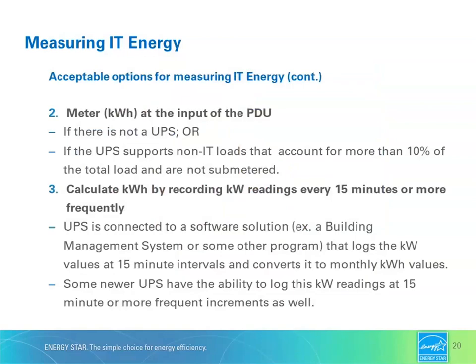So on to option number 2, metering at the PDU input. You can do this in two situations. First, if there's no UPS. Most data centers do have a UPS, but if yours does not for whatever reason, then you can meter at the PDU input. The second situation is the one we just talked about on the previous slide.